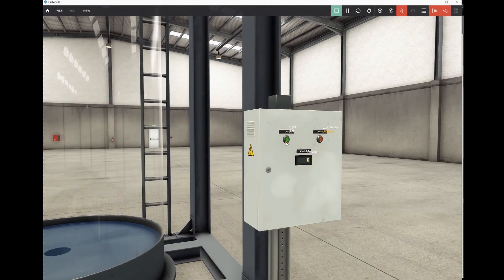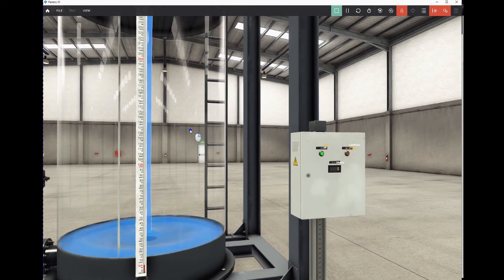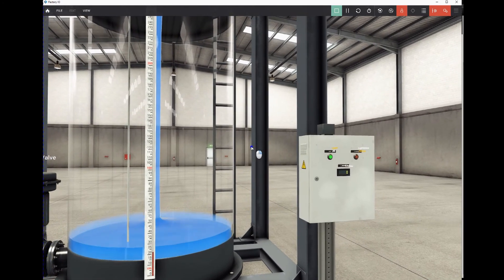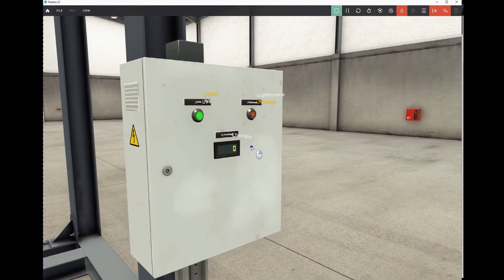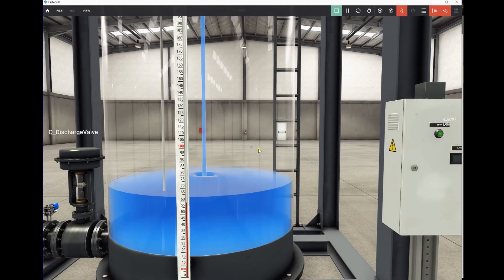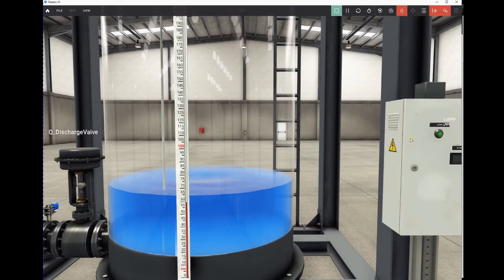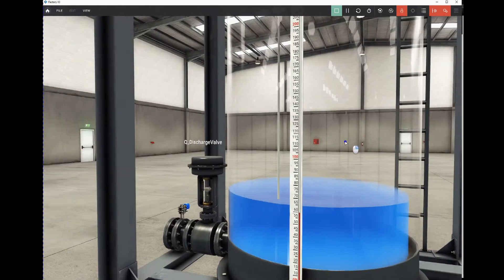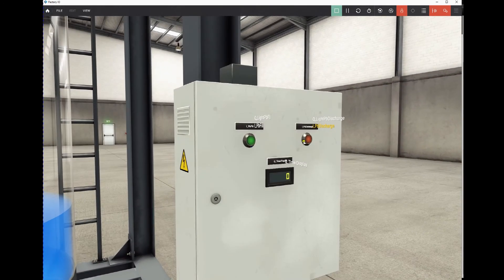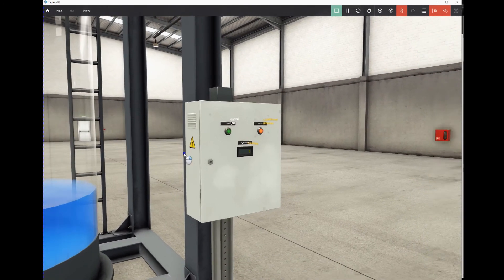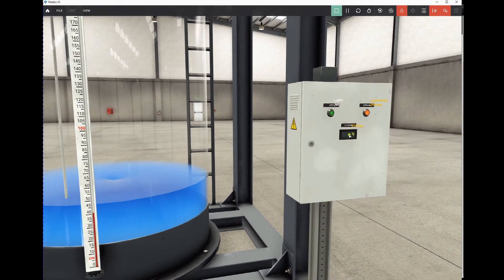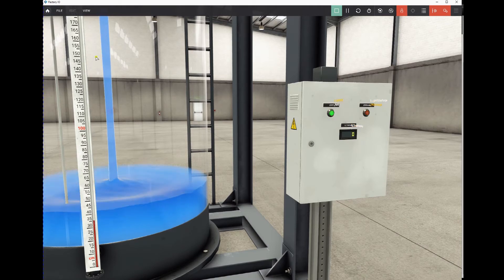Now if you press the fill button, it will fill. For some reason timer display is not showing up. And if you discharge, you will discharge and you will notice the time is counting now. So why is this happening? Why if you press the filling push button the display is not showing? So let's go back to the PLC editor.